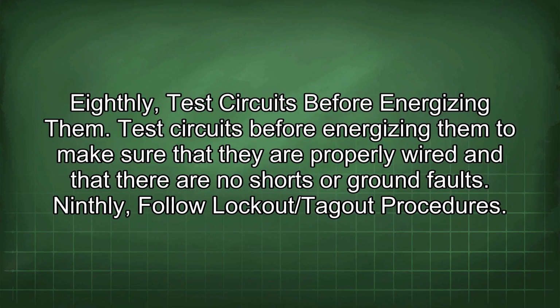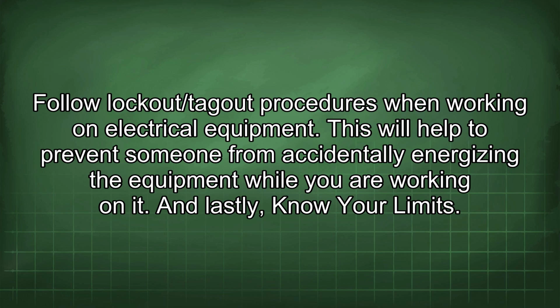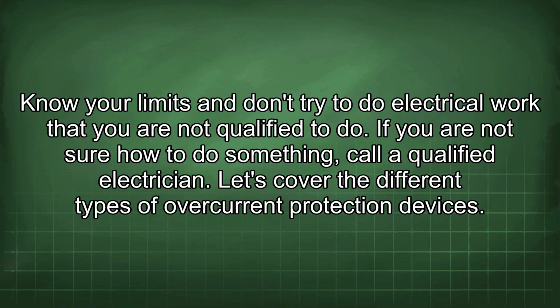Eighthly, test circuits before energizing them. Test circuits before energizing them to make sure that they are properly wired and that there are no shorts or ground faults. Ninthly, follow lockout/tagout procedures. Follow lockout/tagout procedures when working on electrical equipment. This will help to prevent someone from accidentally energizing the equipment while you are working on it. And lastly, know your limits. Know your limits and don't try to do electrical work that you are not qualified to do. If you are not sure how to do something, call a qualified electrician.